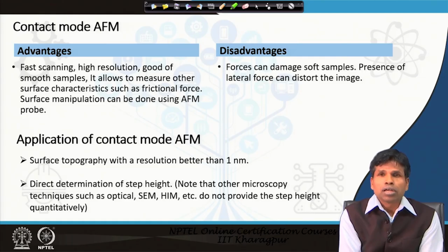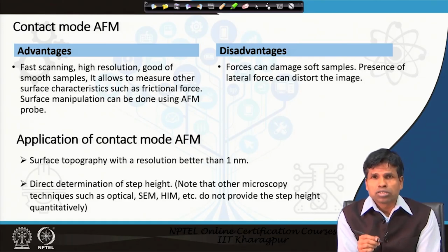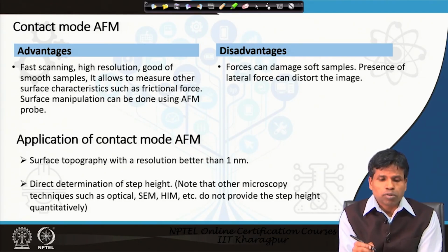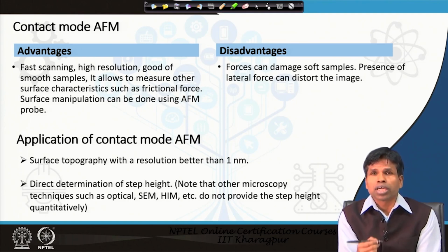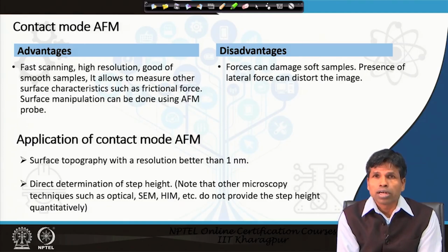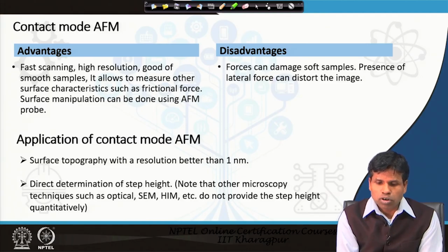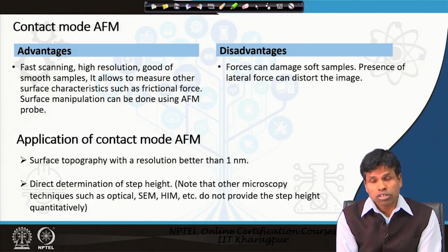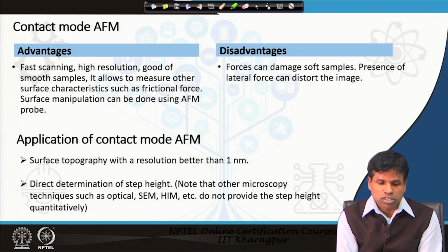Moreover, as the tip is touching the sample surface, we can measure the frictional force and lateral force of the sample surface, which we cannot measure by other modes, like when the tip and sample are not in touch with each other. Disadvantages: force can damage the soft sample. The presence of lateral force can also distort the image. You will see later how it can distort the image.